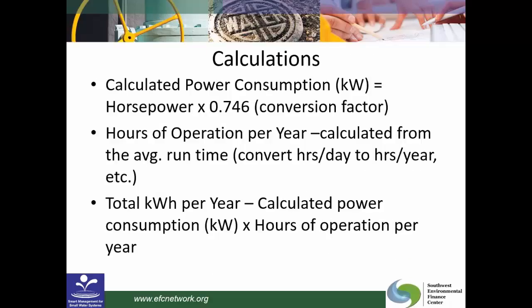Then you start getting into your calculations. So you want to make sure that you've got your spreadsheet set up. The first thing that you're going to do is convert that nameplate horsepower to kilowatts. And it's a simple multiplication. You take the horsepower, multiply it by 0.746, and that converts it to kilowatts.